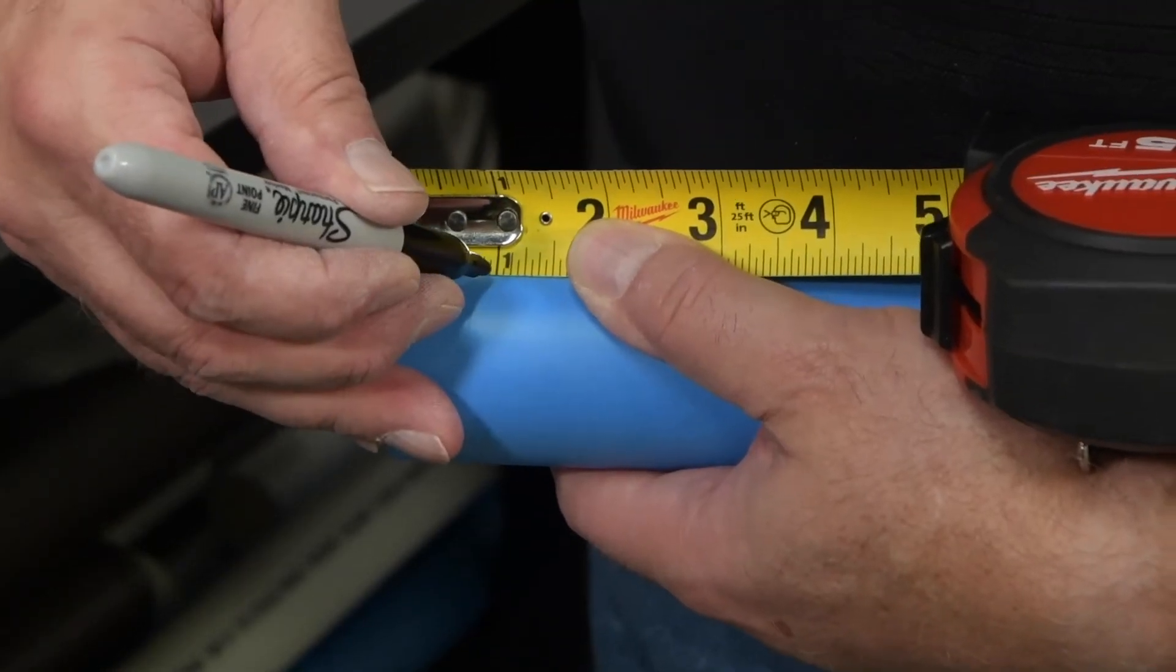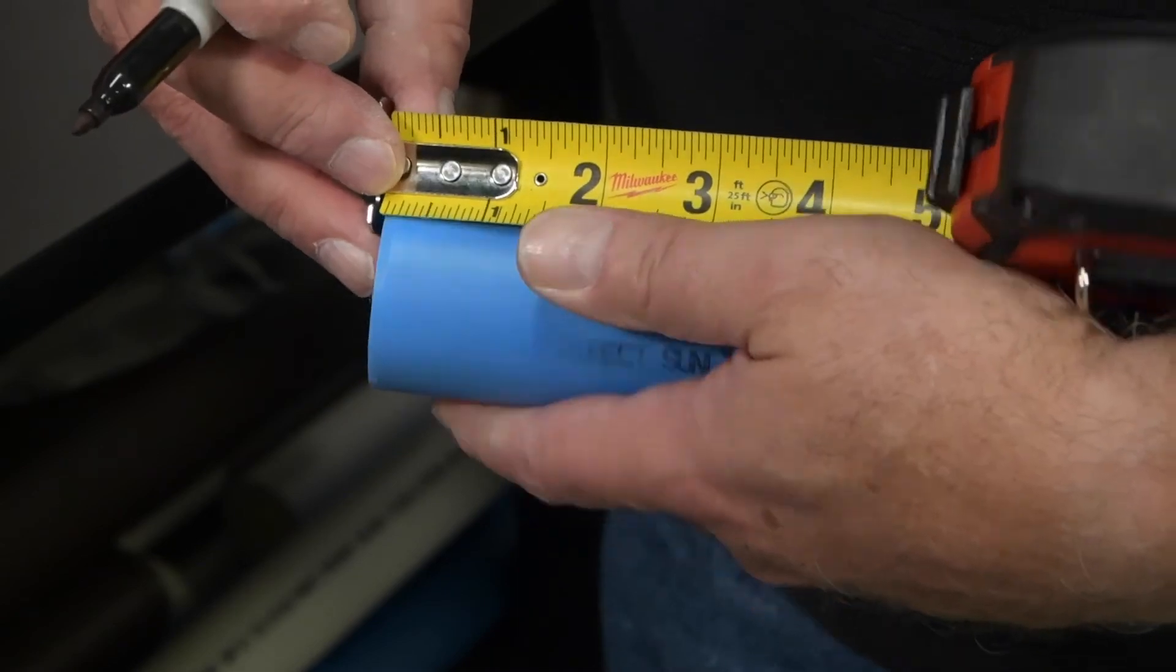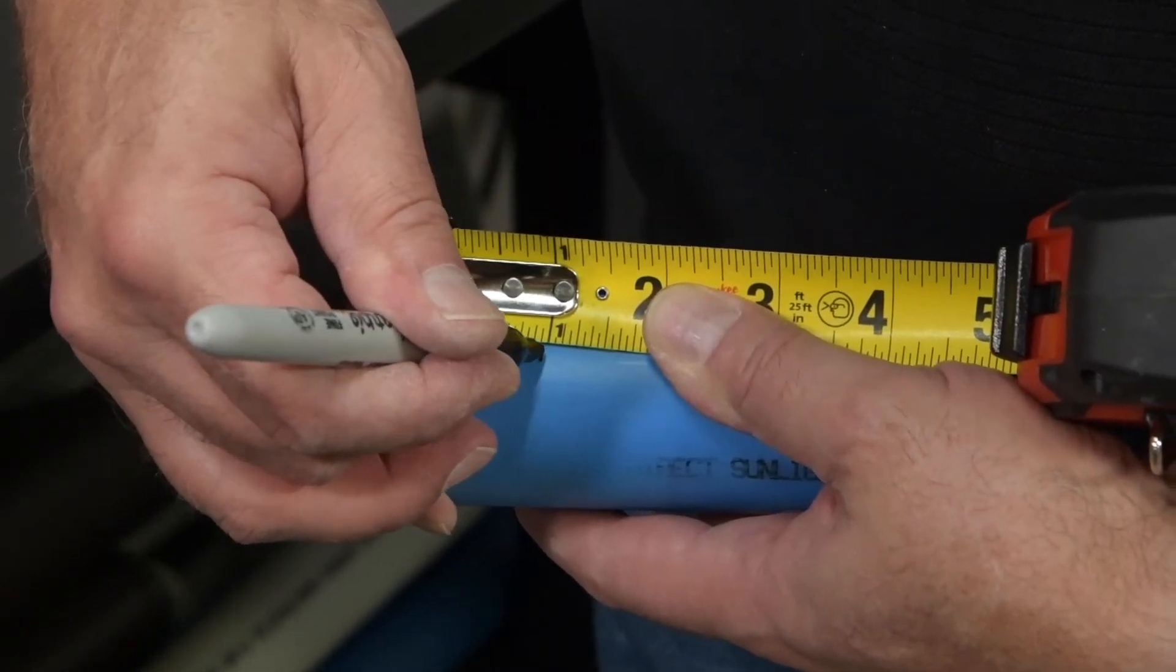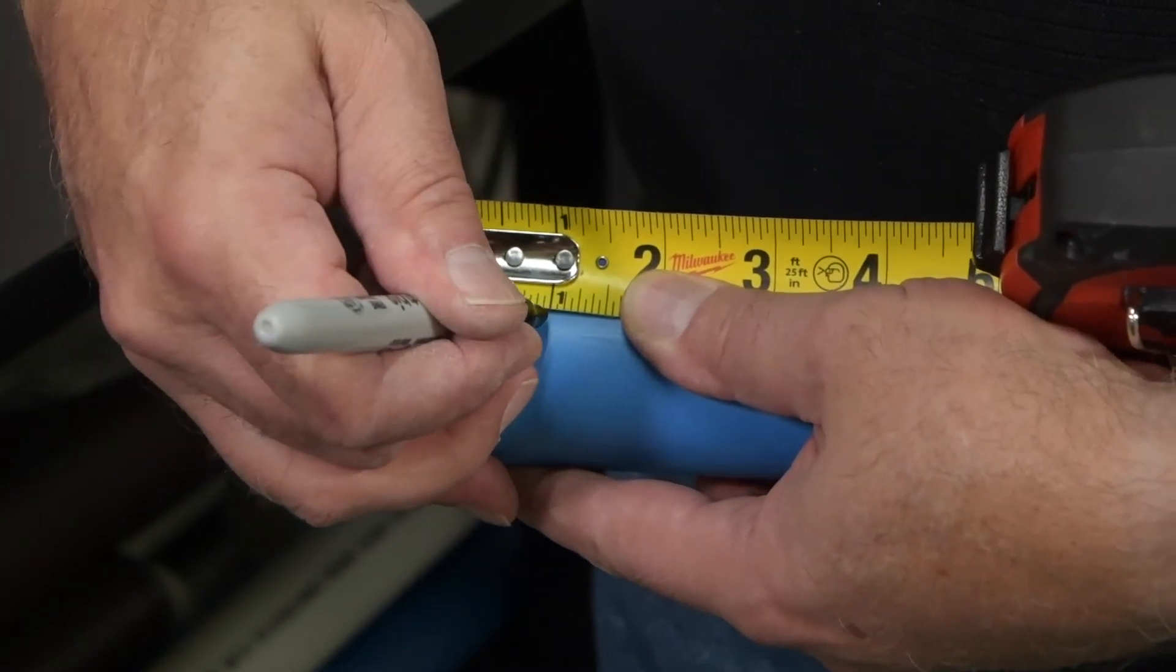Measure the depth of the fitting socket to be fused and subtract 1/16th of an inch. Transfer the fitting socket measurement to the end of the pipe to be fused. Mark the pipe so the measurement will be seen when inserting the pipe into the tool head.